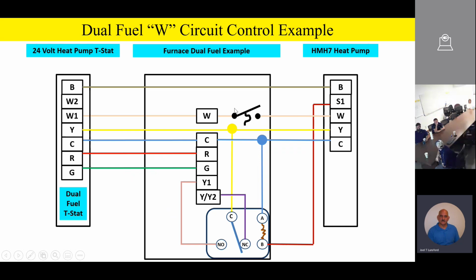So the idea is, again, this little switch right here, that little construction thermostat, we're going to be breaking the W wire from the outdoor unit to the indoor unit on a gas furnace. And when we do that, it'll prevent that short cycling of the furnace. And by the way, we do have a service tip letter that was launched about 3 or 4 days ago that outlines this. And if you don't have that, be sure and get up with me later on, or let's make sure that your regional account manager gets that to you.